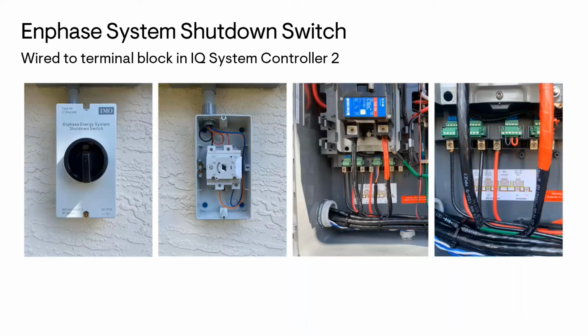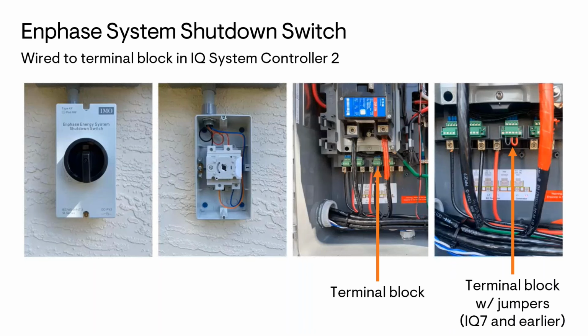It's wired into a terminal block that's located right here in the IQ System Controller 2. Now this terminal block that's pictured doesn't actually exist in the original IQ System Controller, and this is the reason why only the System Controller 2 can be used with IQ8s, because we need to have the system shutdown switch with IQ8s on the solar array. If the IQ System Controller 2 is being used with IQ7s or earlier, the rapid shutdown switch isn't required, but you would need to actually install a couple of little jumpers into this terminal block in order for it to function properly. That's depicted on the far right here.